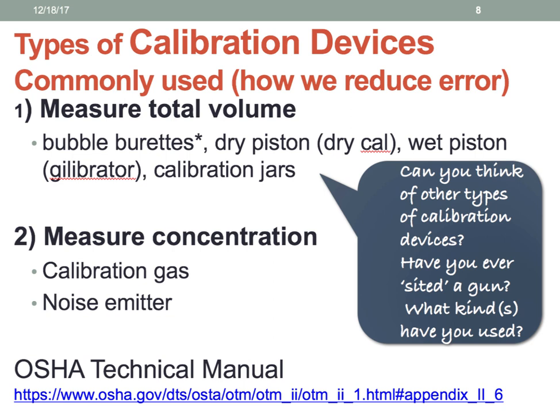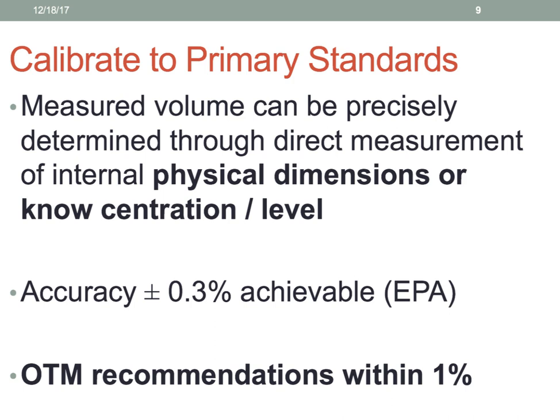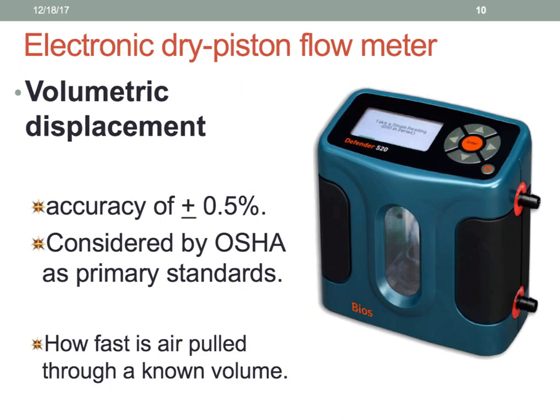Bubble burettes are now considered secondary standards, although some people still use them as primary standards. For measured concentrations, we have calibration gas or noise emitters. Our primary standards are within 1% error rate, as recommended by the OSHA technical manual. That is one of the reasons why they recommend the use of a volumetric displacement device — our dry cal — which is within 0.5% accuracy. OSHA considers this a primary standard and it measures how much air is being pulled through our sampling device.